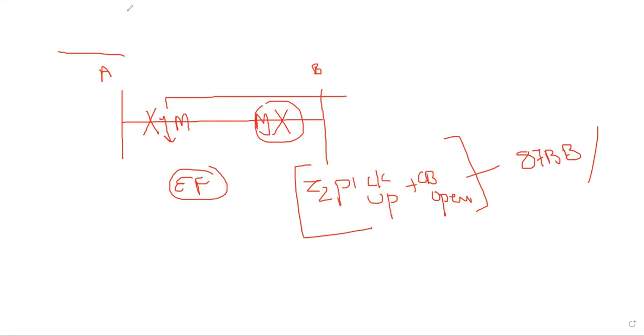One more thing. End fault protection means there is a fault on the line, but the breaker is in open condition when I am charging the station. In that case, when I am closing the breaker, I am closing onto the fault, right? So it should not be done. So I am giving the signal to the busbar differential protection. Yes, that means you are saying SOTF, switch on to fault, right? Switch on to fault is the case when you are closing the breaker on the line during a fault. Okay, you are saying the same.